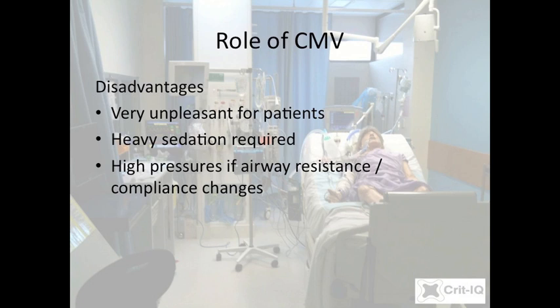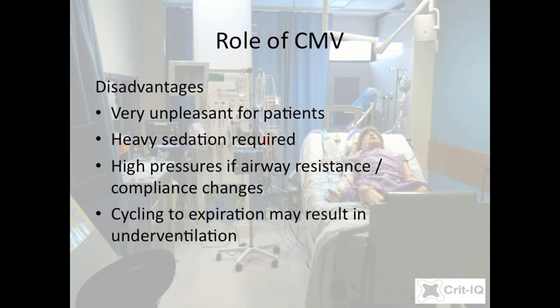To prevent this, an upper pressure limit and alarm is often set. Once this pressure limit is reached, the ventilator will cycle into expiration. While this will potentially protect the lung from further damage, it will also markedly reduce ventilation unless the underlying problem is immediately addressed.